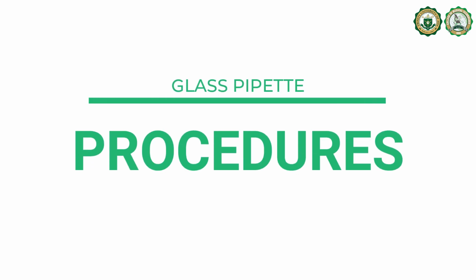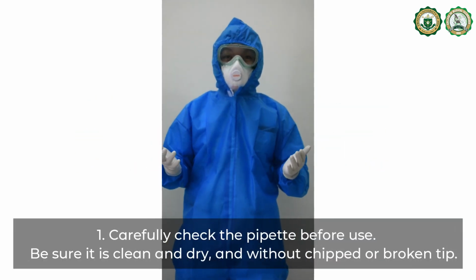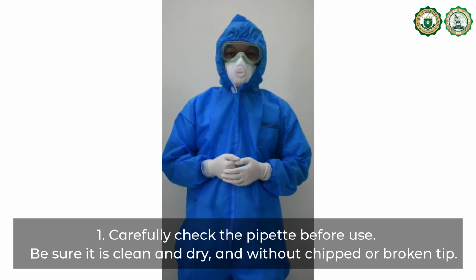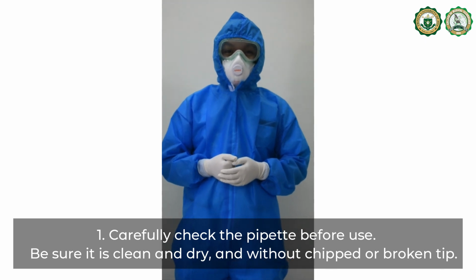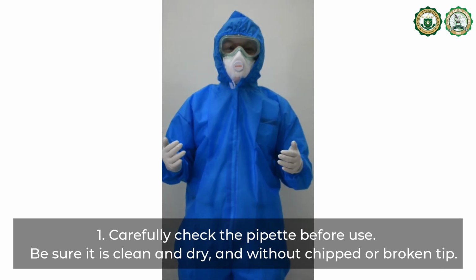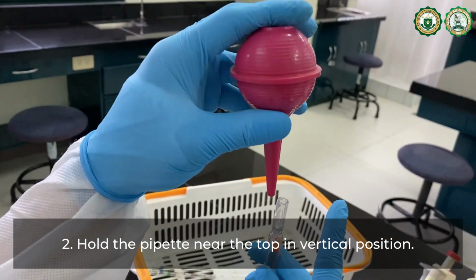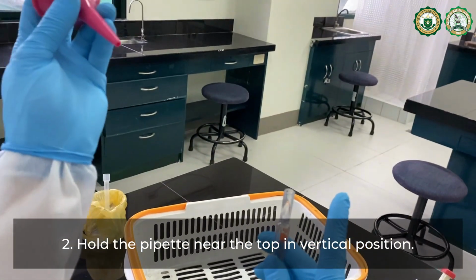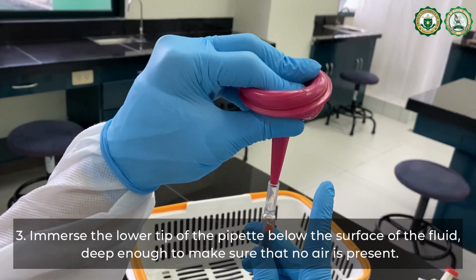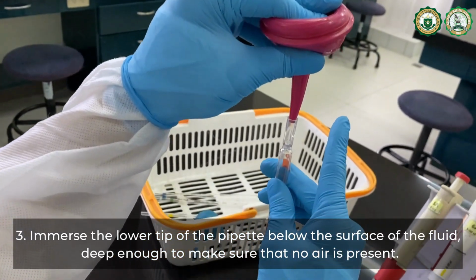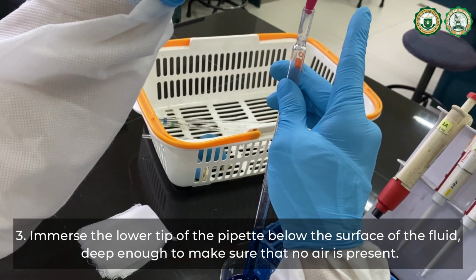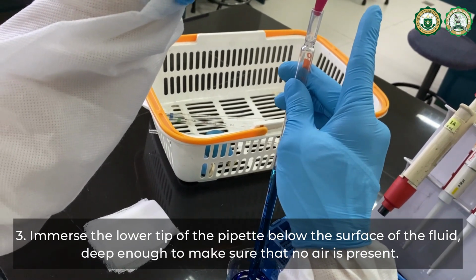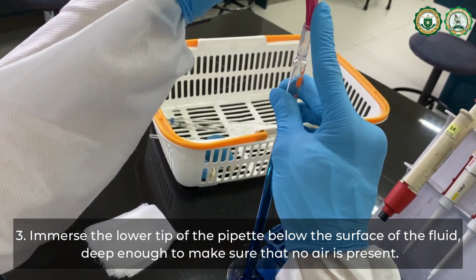For the procedures for manual pipetting, make sure that you carefully check the pipette before use. Be sure it is clean and dry and without chip or broken tip. Now hold the pipette near the top in vertical position. Immerse the lower tip of the pipette below the surface of the fluid. Deep enough to make sure that there is no air present.